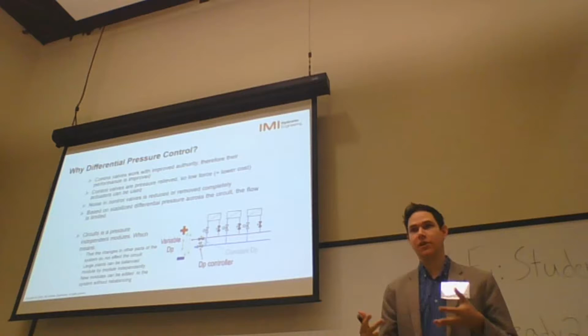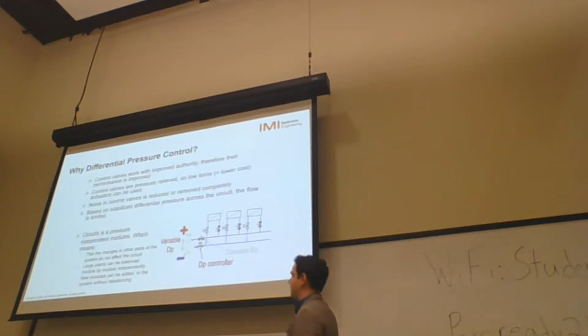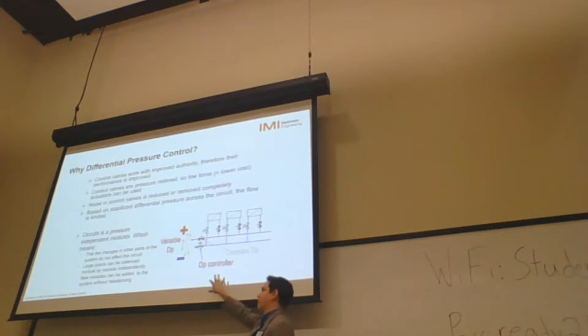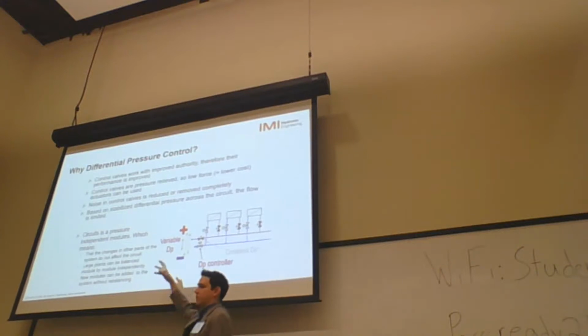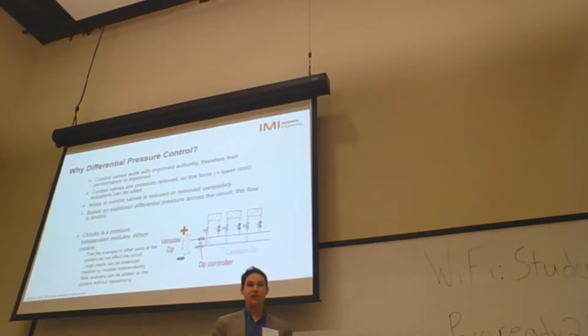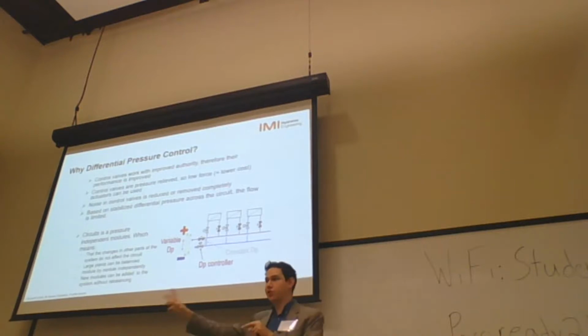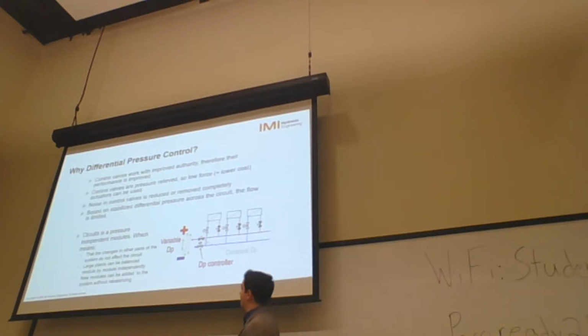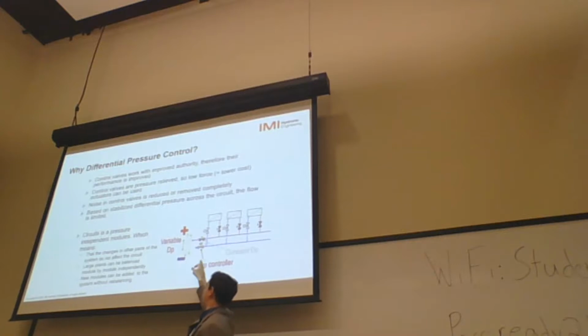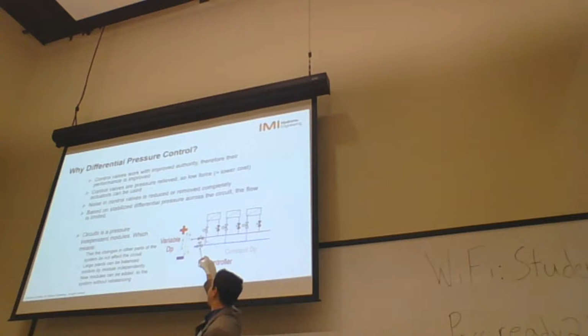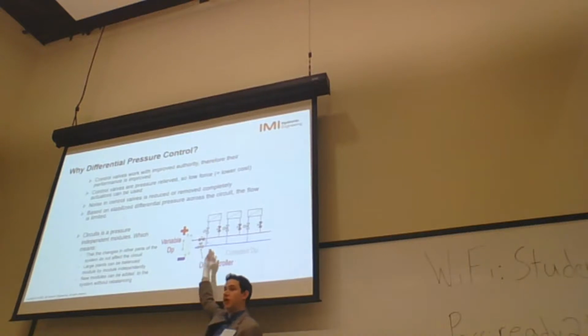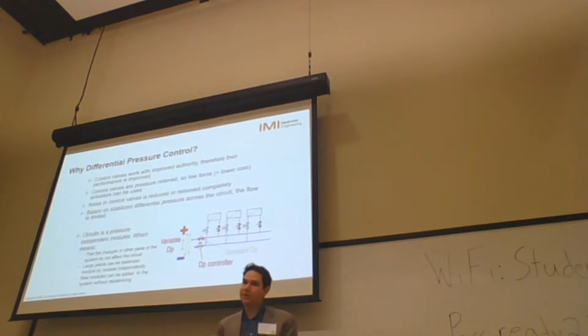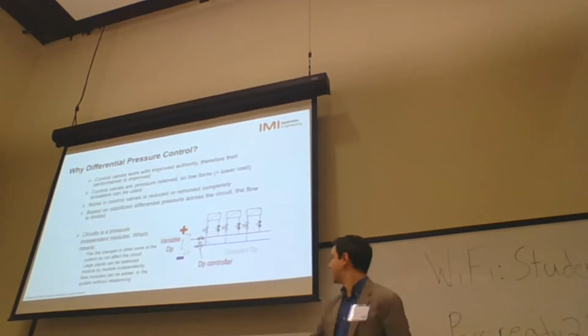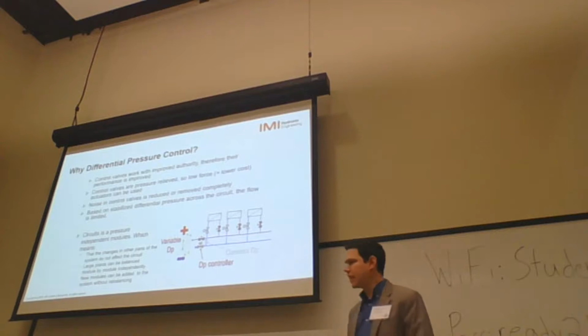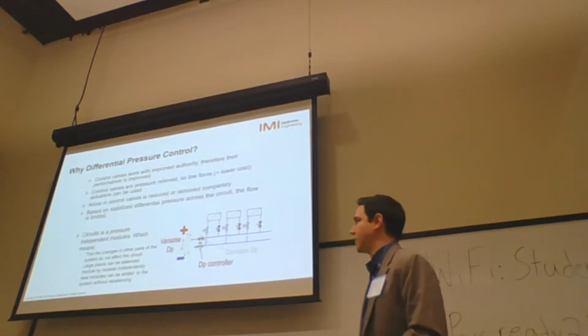But the main concept, the main point that is important for us to understand is on this drawing right here in the bottom right. You do have a variable DP in your system. It could be during commissioning, during balancing, because of the interactions that you have when you're changing one part of the system, opening another part, or even the partial loads in your system. So you do have the variable DP getting to the branch. The differential pressure controller will make it a stable differential pressure getting into the branch. So basically keeping a stable differential pressure to those 3 coils in this example and making the branch pressure independent.